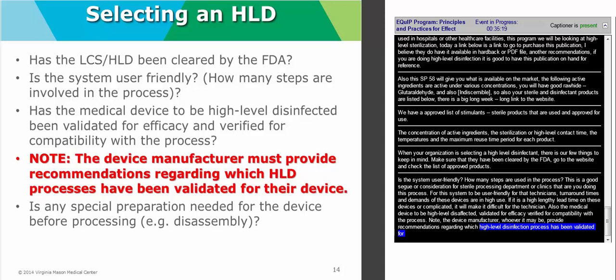Sometimes inspection using magnification might identify any residues more readily than the unaided eye, and visual inspection alone sometimes may not be sufficient for assessing the effectiveness of a cleaning process. And why is that important? Because the organic matter that's left on a device can dilute or inactivate active ingredients in a high-level disinfectant, and it will interfere with its contact to the device surfaces. So the high-level disinfectant won't be able to penetrate through any leftover residues or bioburden on the surface of a device.